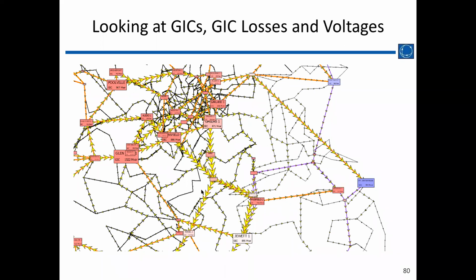It's been our experience that things like zone 3 relays, generator over frequency and under frequency devices, are generally not populated to great detail in transient stability models yet. But if you do have that information, in theory it could be put in there, and I think it would benefit the industry as the focus on HEMP events and preparedness grows. Then certainly populating the transient stability models with those details would be important.